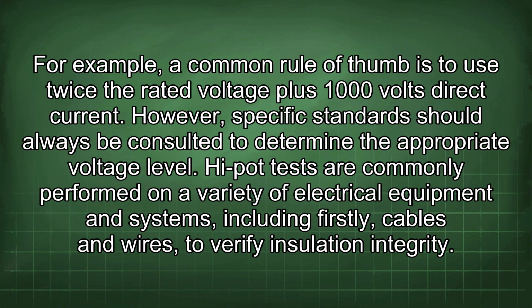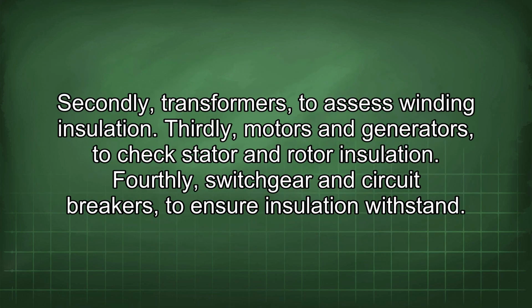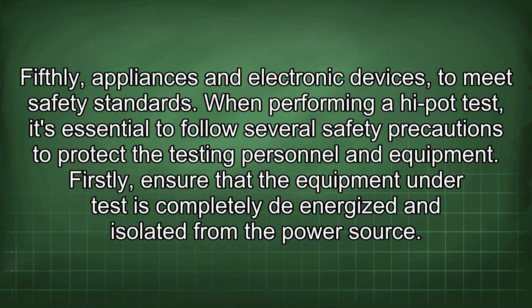Hi-pot tests are commonly performed on a variety of electrical equipment and systems, including firstly, cables and wires to verify insulation integrity. Secondly, transformers to assess winding insulation. Thirdly, motors and generators to check stator and rotor insulation. Fourthly, switchgear and circuit breakers to ensure insulation withstand. Fifthly, appliances and electronic devices to meet safety standards.